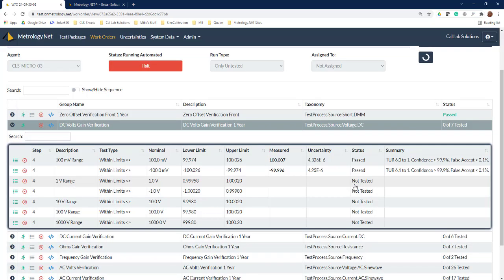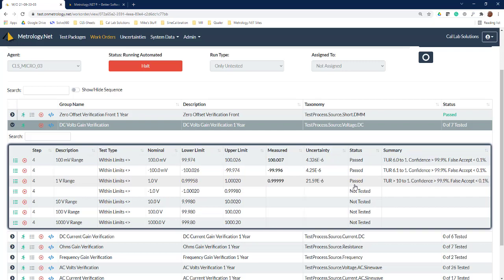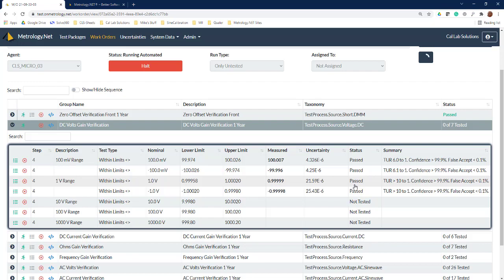Now we'll let it continue the calibration and you can see that at each data point we're posting out our results. So if we were to lose power on this calibration, we're only going to lose the data point that we're working on—we don't lose any of the other data points.